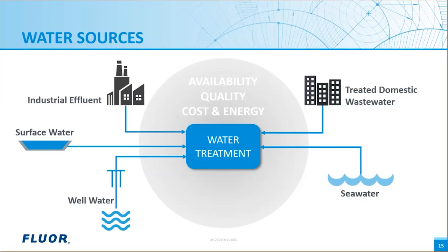Lastly, industrial effluent. The quality and availability will be entirely dependent on the industry. It may require low levels of treatment depending on the waste quality and user requirements. In some cases, it can bypass treatment altogether prior to use. It's important to realize that this will introduce complexity to the design, as a source facility may have excursions in composition and availability during periods that may not always align with the operation of the consumer.